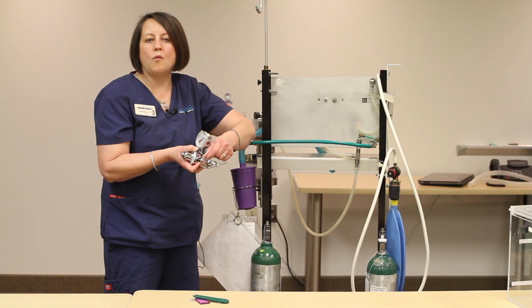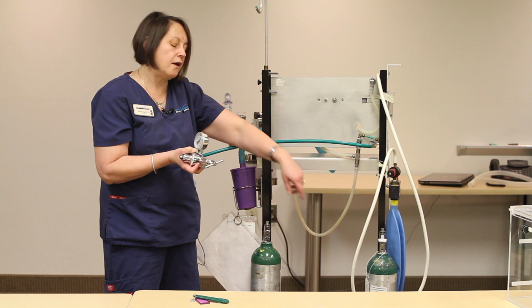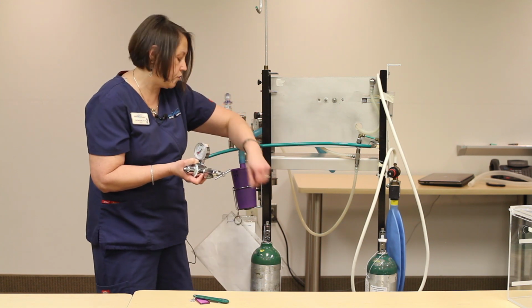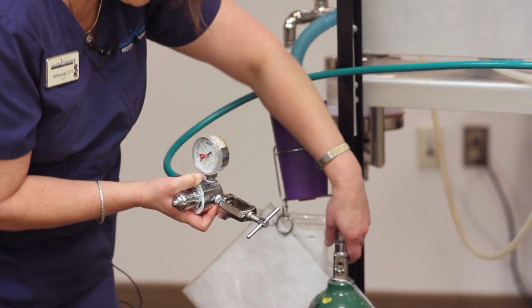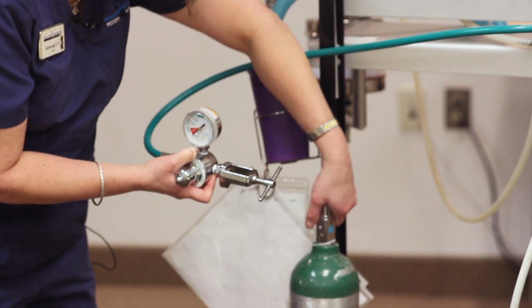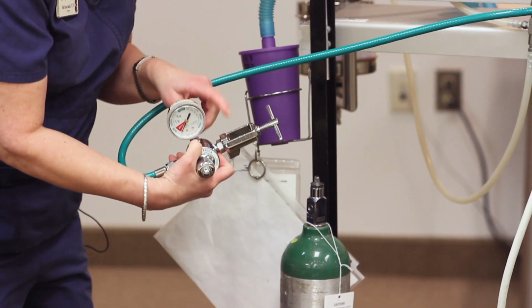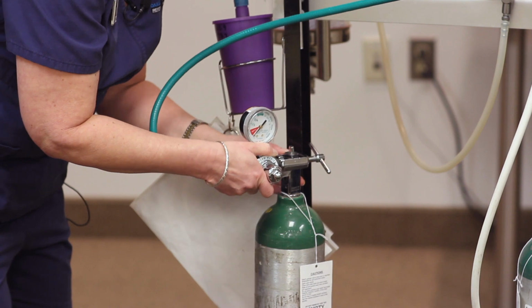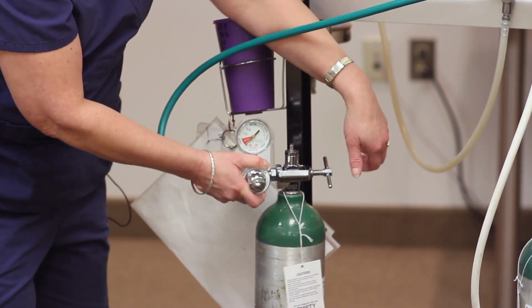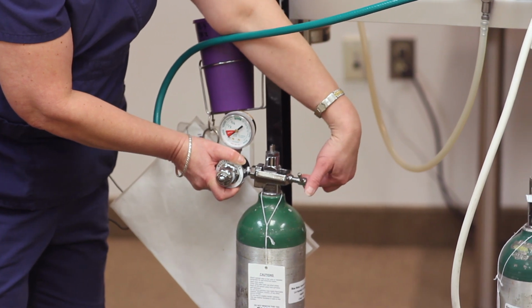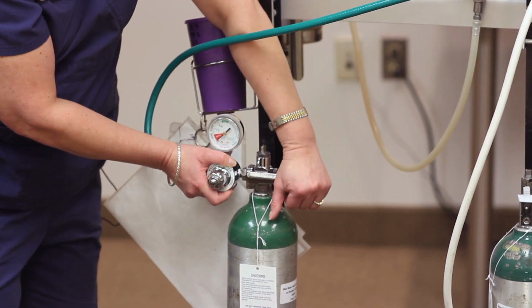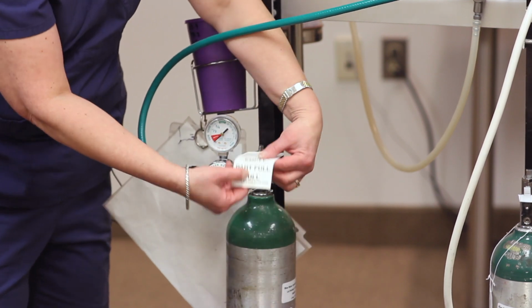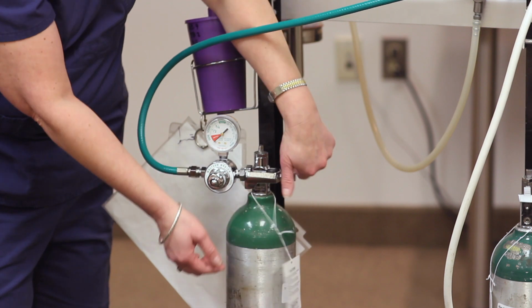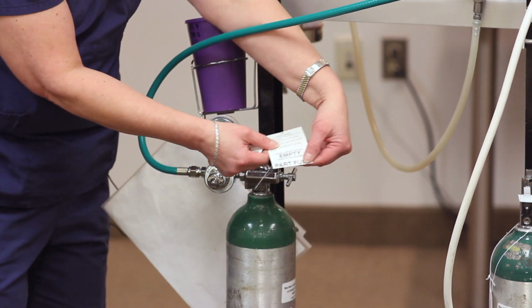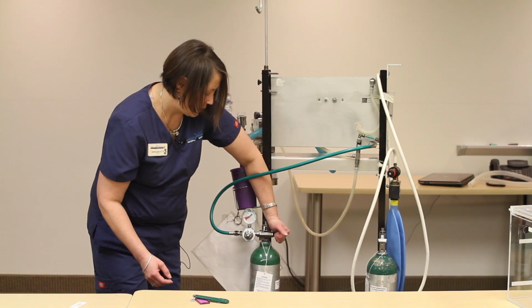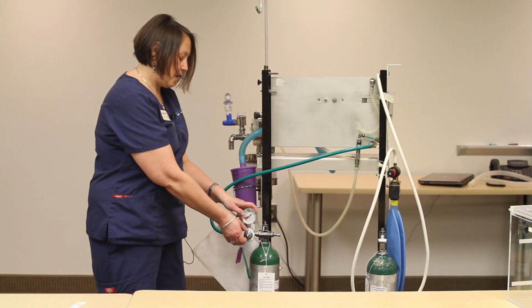There is usually also a washer that comes with the new tank, so please change these as you change your tank. In order to hook that back up, it's very simple. All you need to do is line up the 3 pegs over that part of the oxygen tank and push it in there, and then use this to tighten it right down on there. And then if this tank were empty, we'd rip that off and label it as empty. But right now this one technically should say part full or in use. And that is how to change the oxygen.